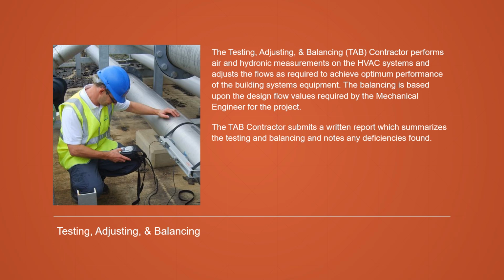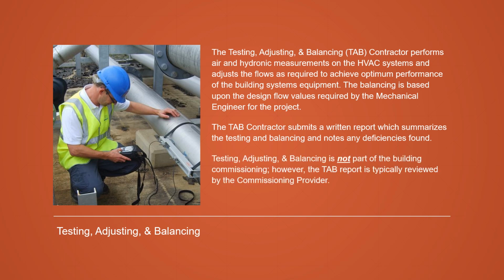deficiencies. Testing, adjusting, and balancing is not part of the commissioning process. It is its own parallel process that is used for HVAC systems. However, the TAB report is typically reviewed by the commissioning provider and often attached as an exhibit to the end of the commissioning report. Commissioning is a broader, comprehensive process that ensures all building systems meet the owner's requirements, whereas TAB specifically targets the performance and efficiency of HVAC systems. Both processes are essential for achieving a well-functioning, energy-efficient building.